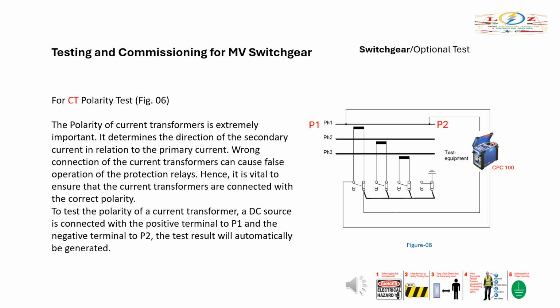Wrong connection of the current transformers can cause false operation of the protection relays. Hence, it is vital to ensure that the current transformers are connected with the correct polarity. To test the polarity of a current transformer, a DC source is connected with the positive terminal to P1 and the negative terminal to P2, as shown in the figure. All results will be recorded on test record sheet.